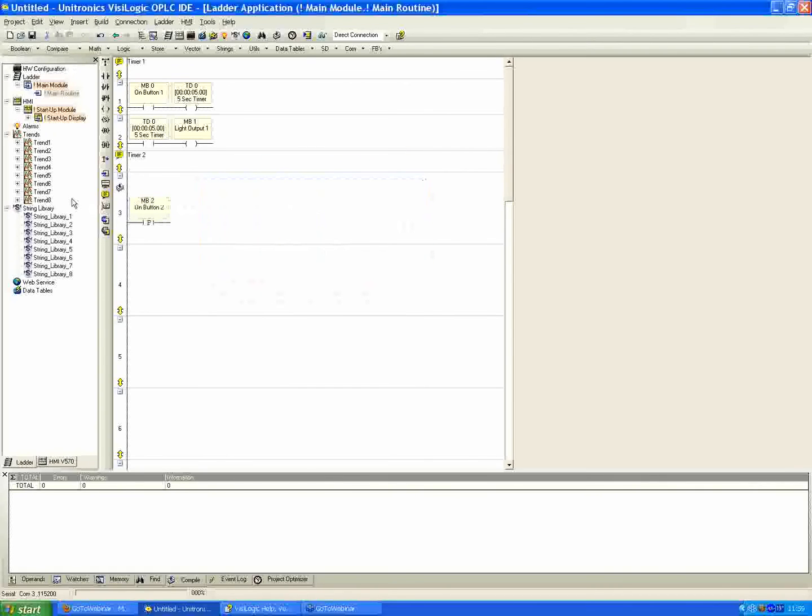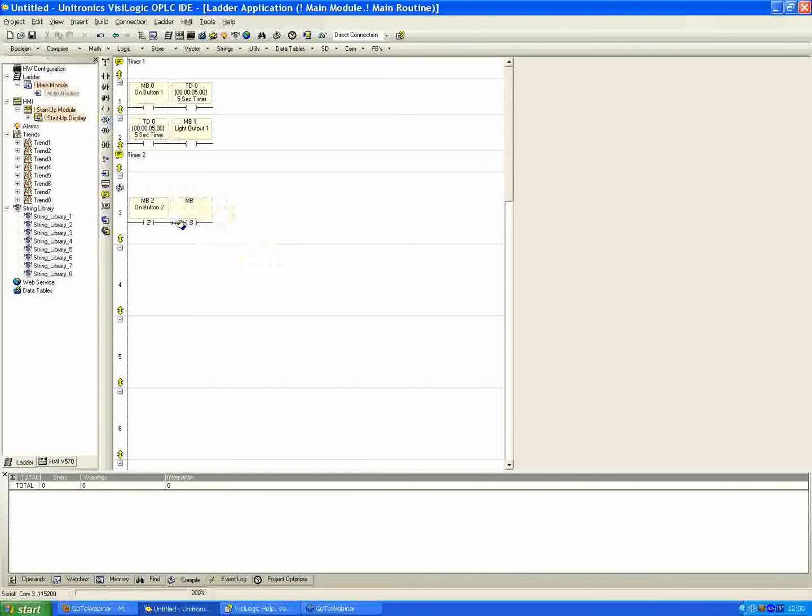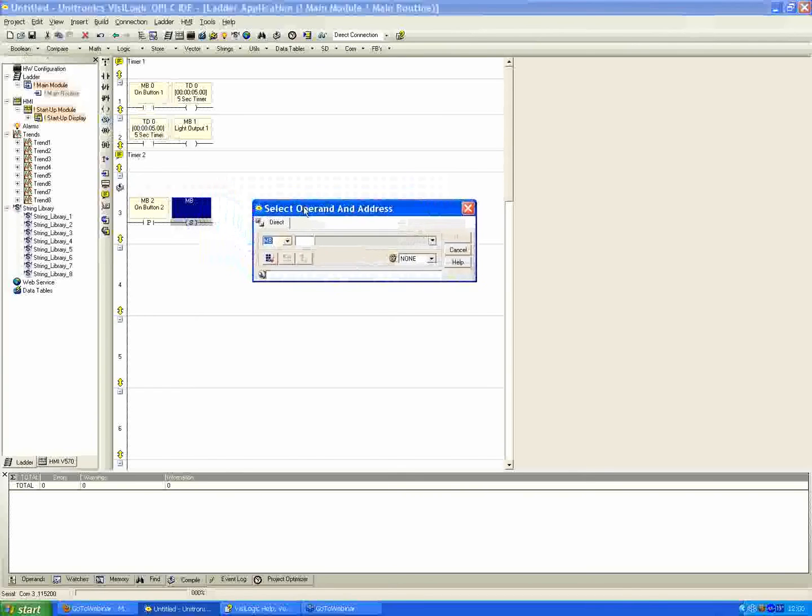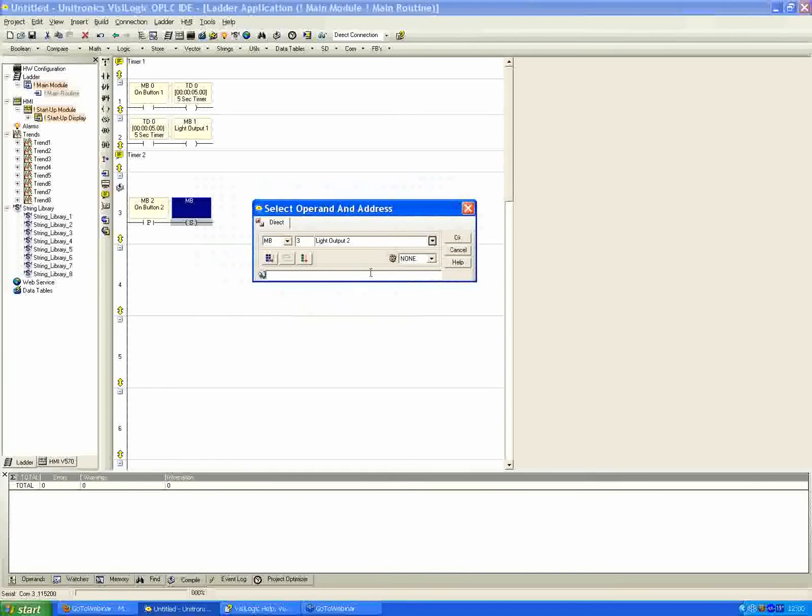Now I said I wanted to make it so you can push the button one time, have the output turn on, and then the timer is going to count down. And once the timer counts down, we're going to shut the light off. So to make that happen, instead of a direct coil this time, we're going to use a set coil. Again, you can just grab that on the middle here or also under the Boolean menu. I'll place that in series.